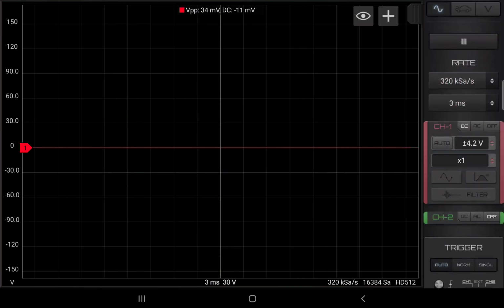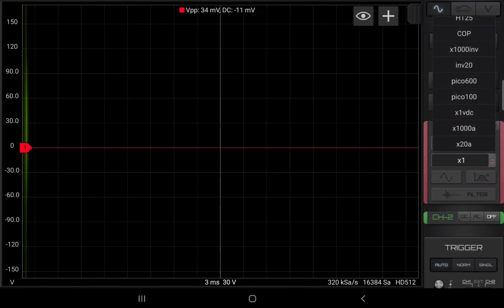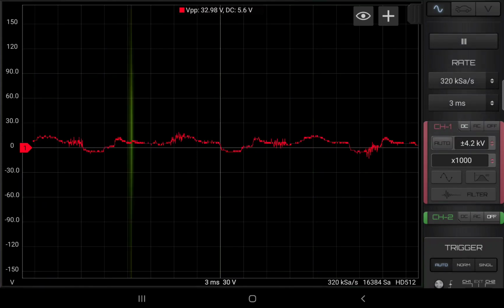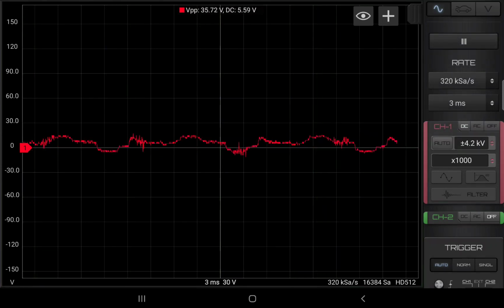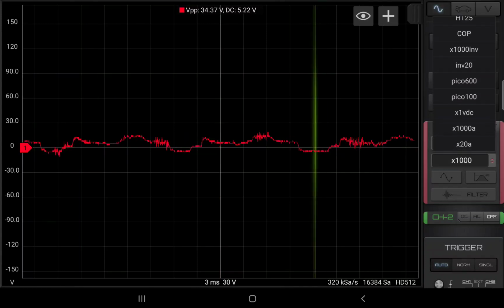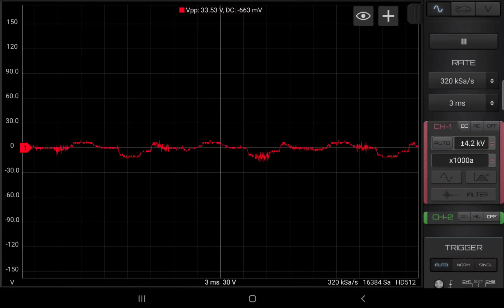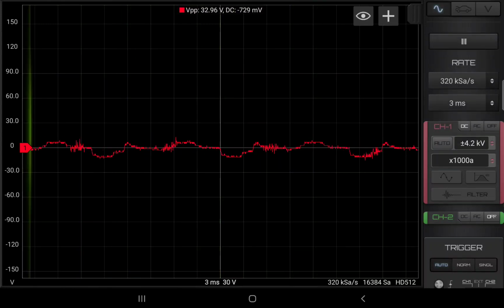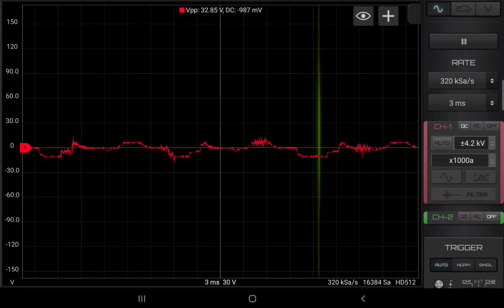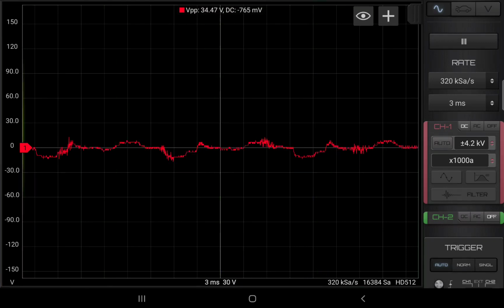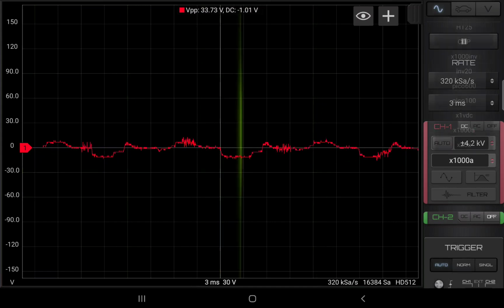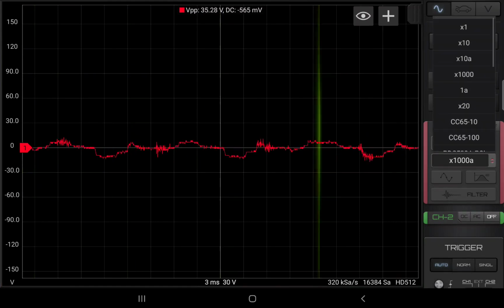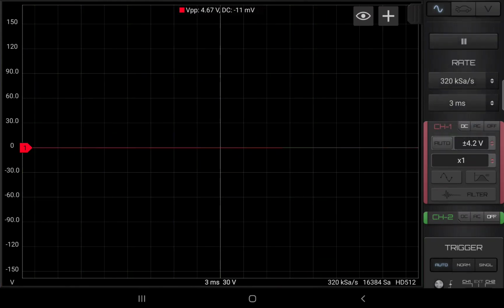So now, again, you can see I go to my 1000. I'm at 5 volts. I go to my 1000A. I start off at about, I'm looking at the top, about 700 millivolts. The other thing is, say I'm going from a times 1000 probe down to a times 1 probe. You always want to cycle both ranges. So I went down to 1, my times 1 probe.